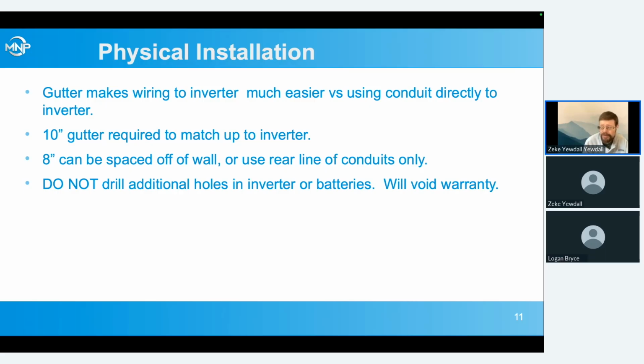If you're doing a full setup with grid tie, AC in, AC out in full 100 amp wire, and some AC smart loads, and a lot of PV inputs and your battery, you're going to find that you don't really have enough room only using the rear line of conduits. If you're just doing an off-grid with 1 or 2 MPPTs, your battery input, an AC output that's not full 100 amp because it's only the output of the inverter, and a generator input maybe, it might be pretty reasonable to just use the rear line of conduits.